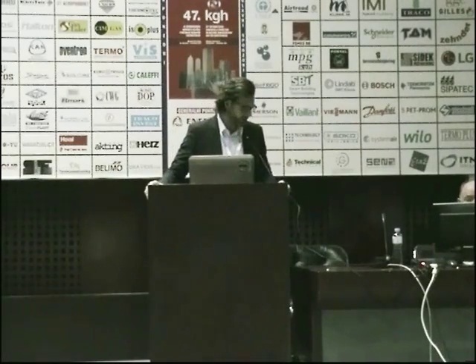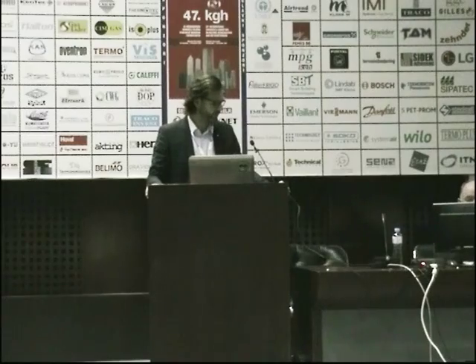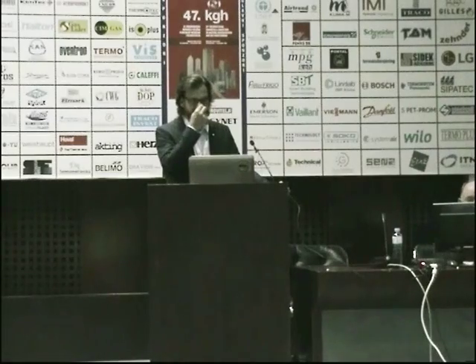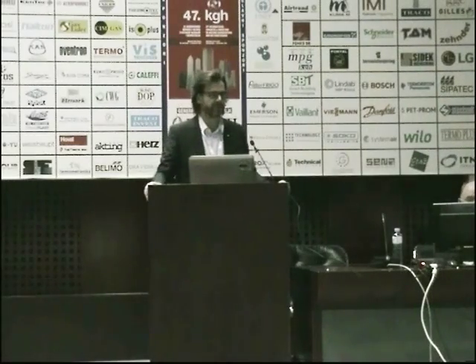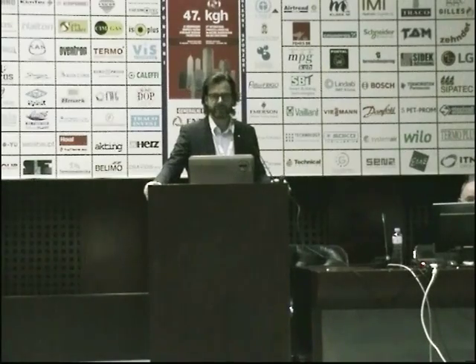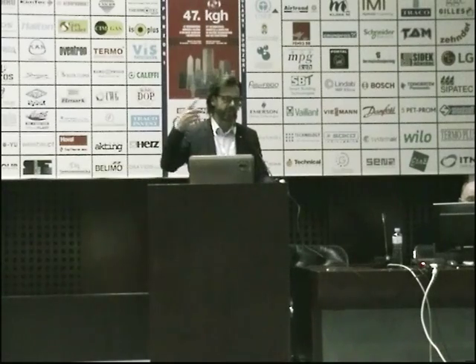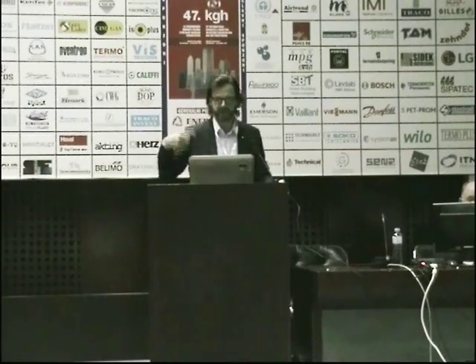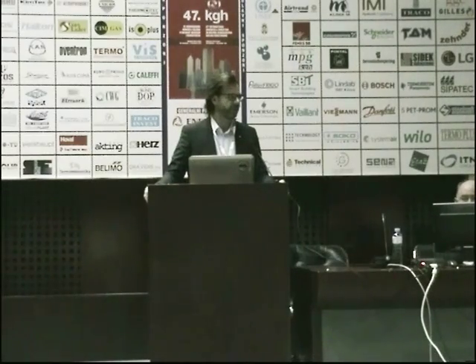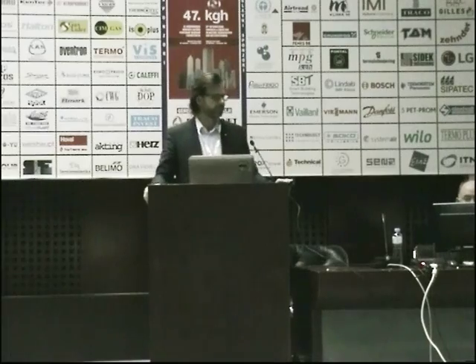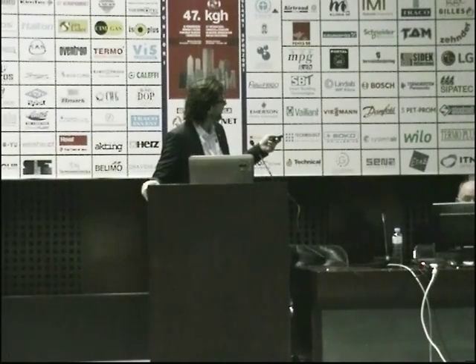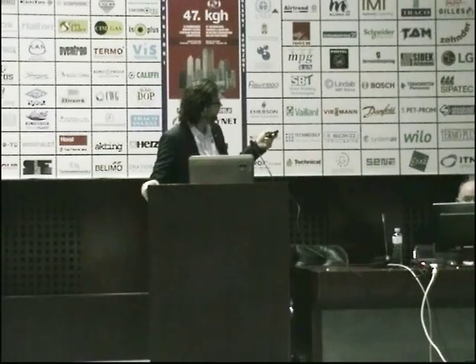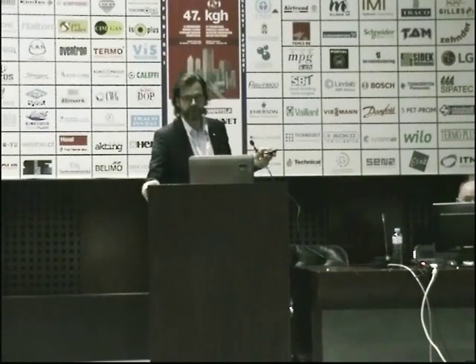This is one, let's say, main point on the side of strength. We did two different system designs because we didn't know how good the heat exchangers in South Africa are manufactured. On one side, we took a second loop where we condensed the CO2 via the brine, via the glycol. On the other side, in Cape Town, a completely rack was bought with a surge drum and then an evaporator heat exchanger for condensing the glycol on the one side and condensing the CO2 on the other side.